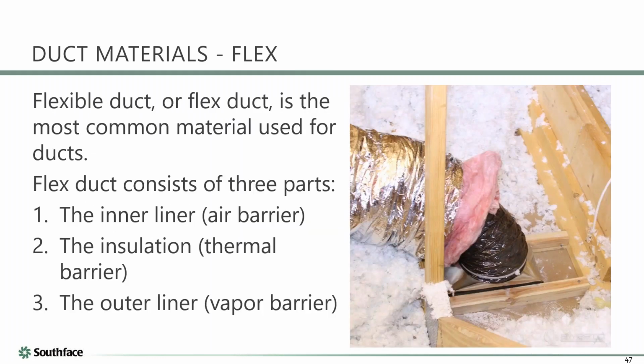What can I say? So Joey, flex duct, 3 main parts. You want to cover these? Yeah, I like this picture because you can actually see all 3 parts here. The first is the inner liner. So that black plastic type material that you're seeing, that is the air barrier. But you'll also notice that it has kind of this wire, to kind of give it some structure. Yeah, slinky. And if you don't put the flex duct in there correctly, that slinky will kind of make what I call speed bumps, and that'll definitely slow down that air. You want something nice and smooth. The second part is the insulation.